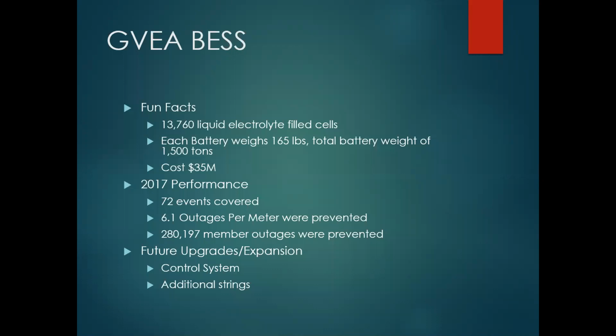Right now, we often size or state the capacity based on how much it can give us for 15 minutes, because 15 minutes is how long it takes to get a turbine spooled up. So if we have a system event, we only want to put out X number of megawatts to give us 15 minutes of runtime. If we just dump it all in 5 minutes, we still drop all the customers because the turbine's not spooled up yet. So right now we can do 27 megawatts for 15 minutes, and that's a moving number based on the state of health of the batteries. Even since I've been employed here, that number slipped from like 29 to 26 and a half, so that's going down.